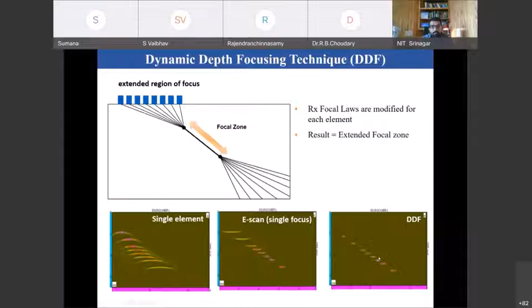We can also focus individually in transmission itself. Not in DDF, where, as I said previously, you focus individually on the reception side, but we can also focus individually at different depths on the transmission side itself, and real imaging can be possible by the multi-point focusing technique. For example, with the same titanium calibration blocks I took for the inspection, it was acquired with 32 elements by focusing at 20, 40, and 60 mm. It requires 3 different visualization windows, and all the defect signals from the low noise and medium noise titanium specimens could be detected clearly with high sensitivity. But this method is not so practical to use because it slows down the pulse repetition frequency, and it also increases the amount of data storage.